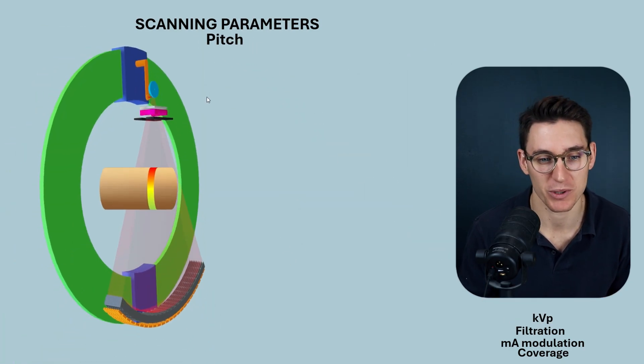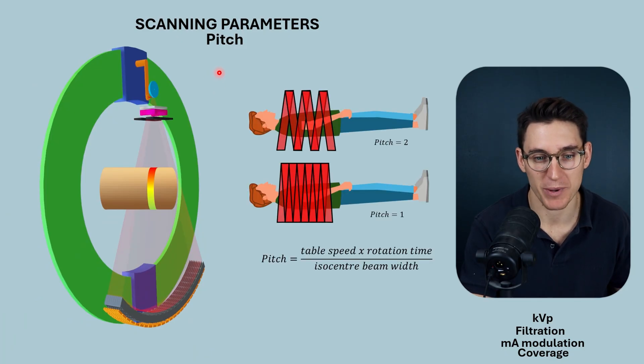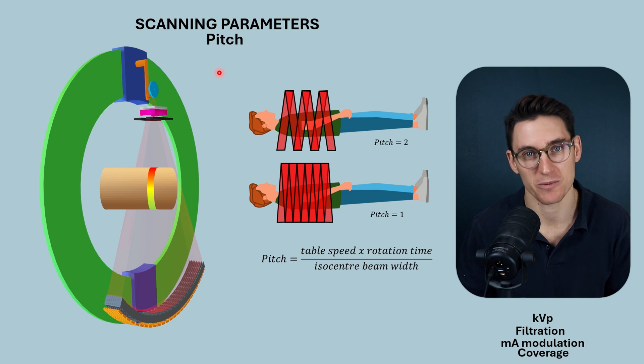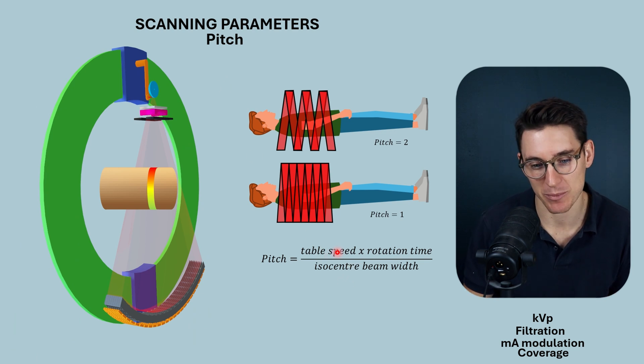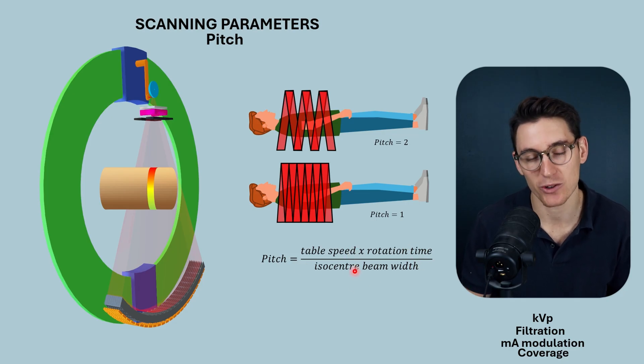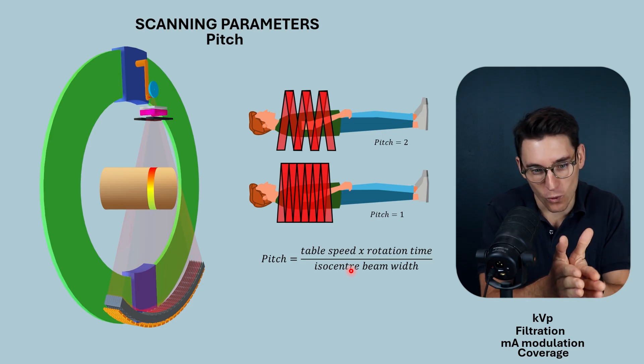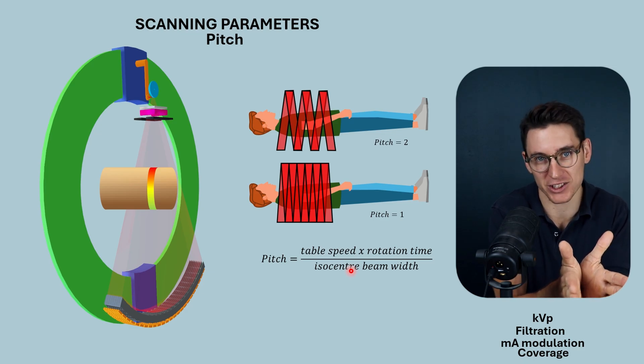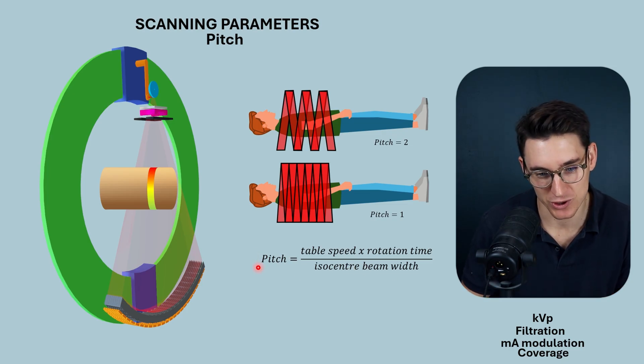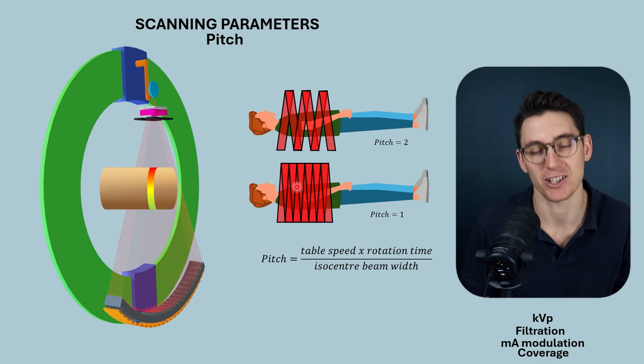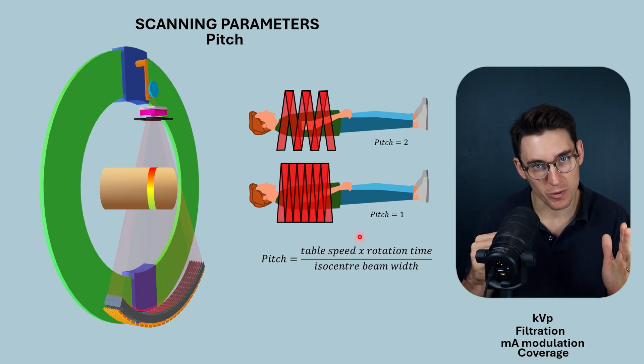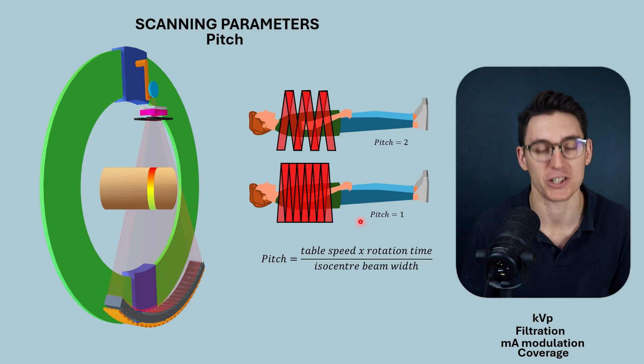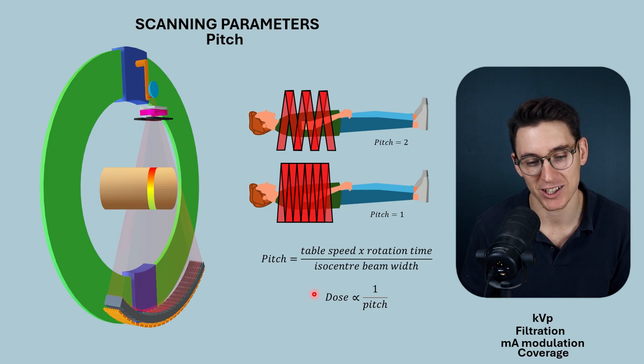Next, we're going to look at pitch, which we covered in the previous talk. Pitch is related to the rate at which the patient moves through the CT scanner — the table speed — as well as how fast the x-ray source is rotating around the patient and the beam width. If we keep table speed and rotation time the same but increase the beam width, increasing coverage in the z-axis and increasing our cone angle, we would be exposing more of the patient to ionizing radiation per rotation, reducing the pitch. A reduction in pitch means an increase in dose.